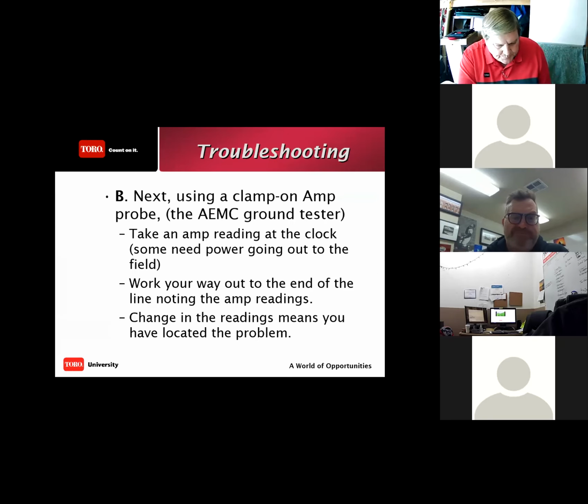Very important. Next, use your clamp meter and isolate the 2 wires far enough apart to get your clamp meter in there and do a reading. Take the amp reading and move through each wire path. And always check every wire. You've got 2 wires, don't just check one and call it good. Check both wires individually. If you've got 6 in that box, you're going to be checking 6 wires individually, one at a time.